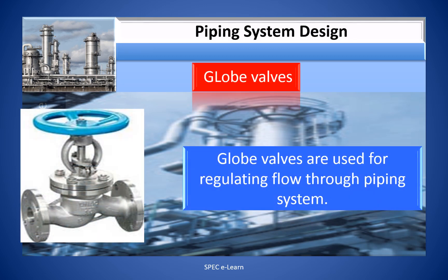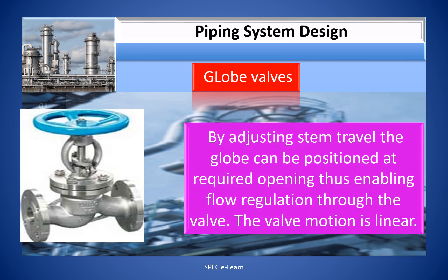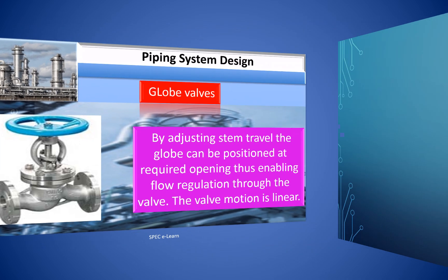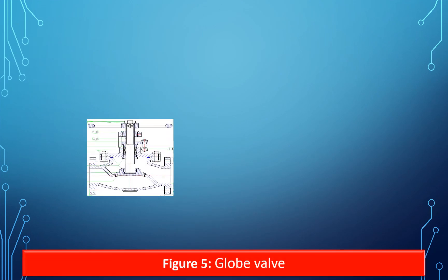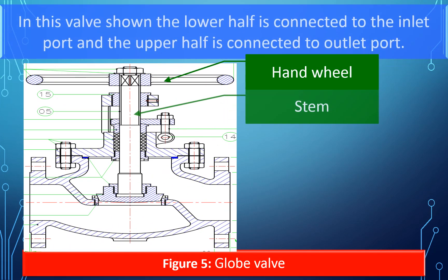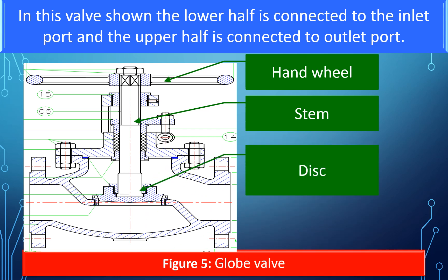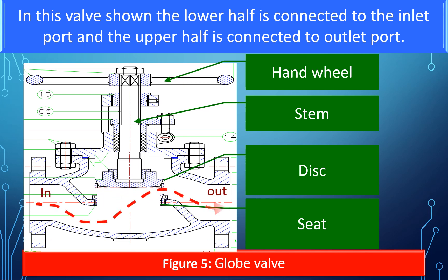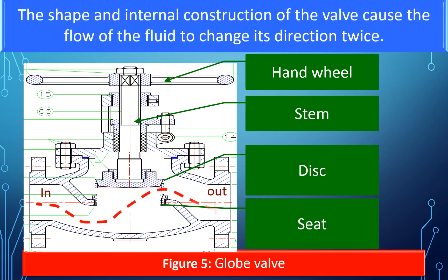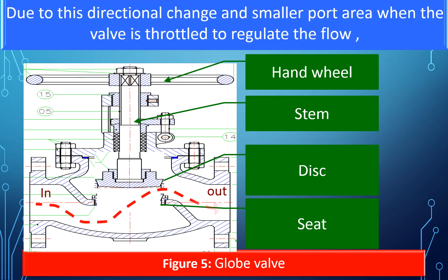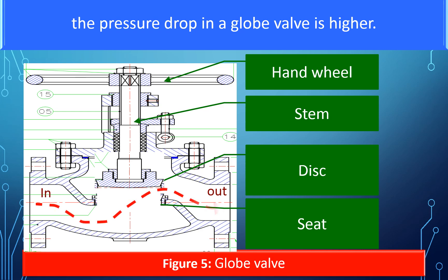Globe valves are used for regulating the flow through the piping system. By adjusting the stem travel, the globe valve can be positioned at a required opening, thus enabling flow regulation. The valve motion is linear. The internal construction of the valve causes the flow of fluid to change its direction twice. Due to this directional change and smaller port area, when the valve is throttled to regulate the flow, the pressure drop in a globe valve is higher.